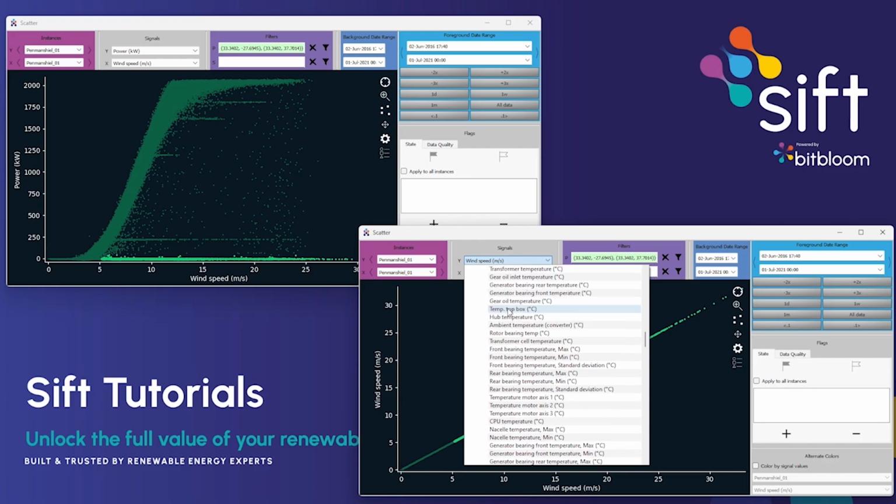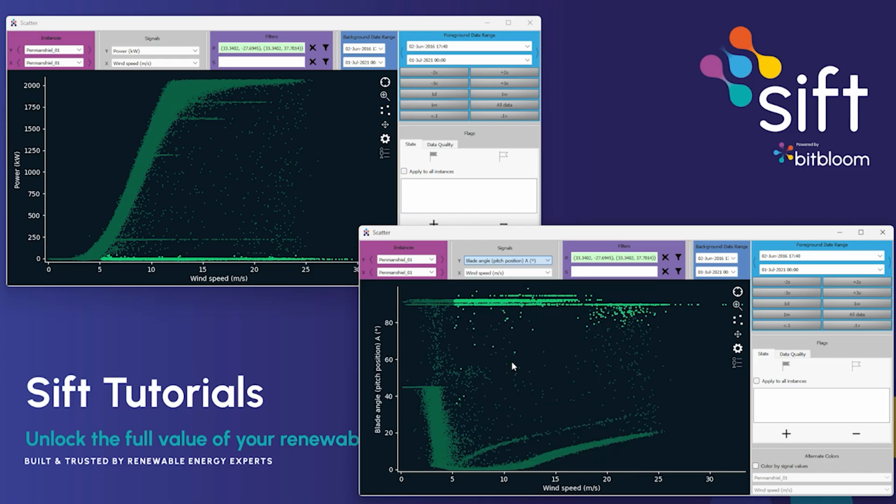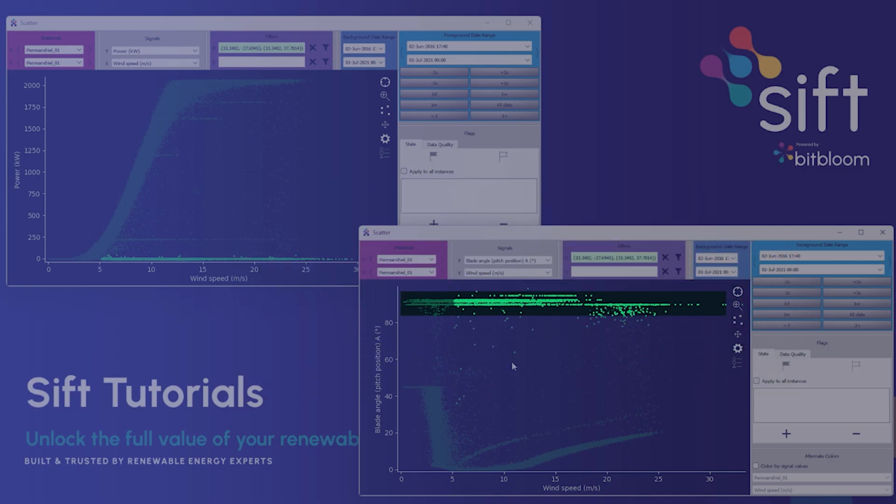The main elements of turbine control are pitch, generator speed, and power. The main brake of a modern turbine is the blade pitch system. At 90 degrees, this turbine is fully stopped. At 45 degrees, this turbine is idling, waiting for the wind to pick up. When the wind picks up, the pitch angle goes down to close to zero. Low pitch angle creates lift, which allows this turbine to produce power. You can see this transition here.